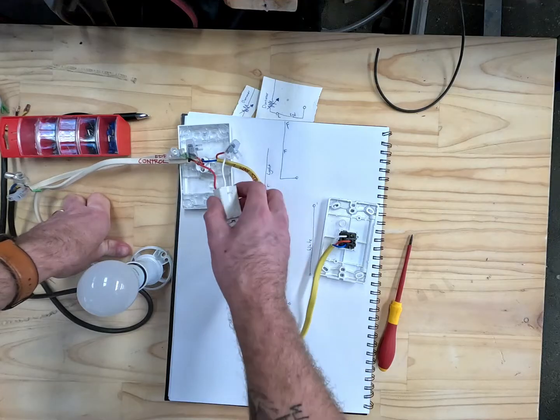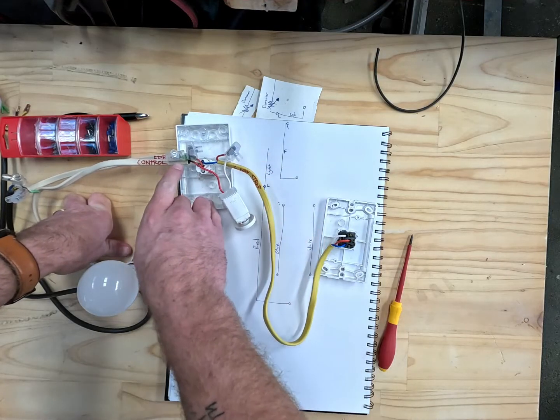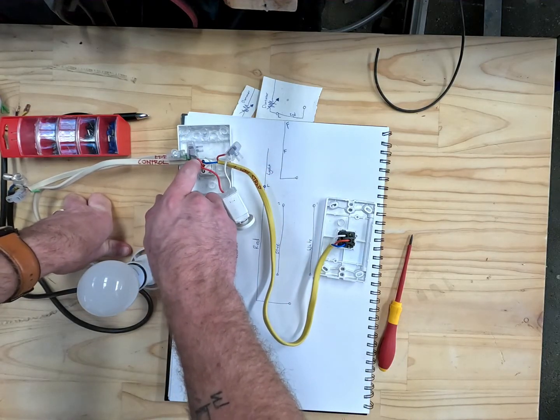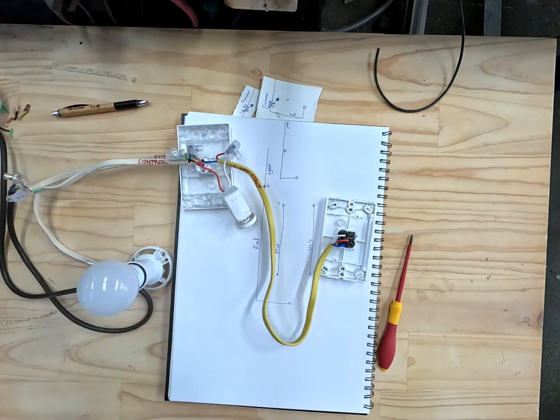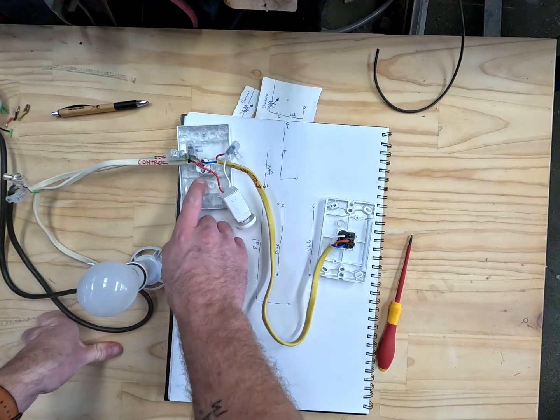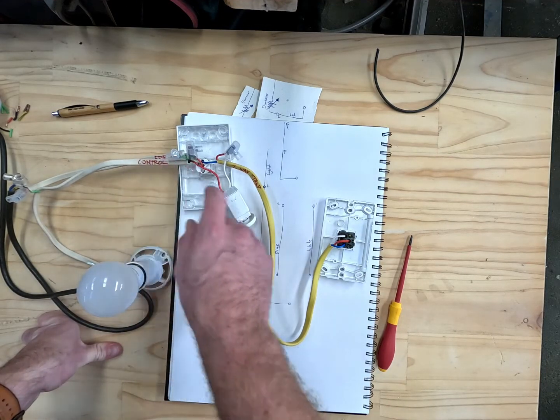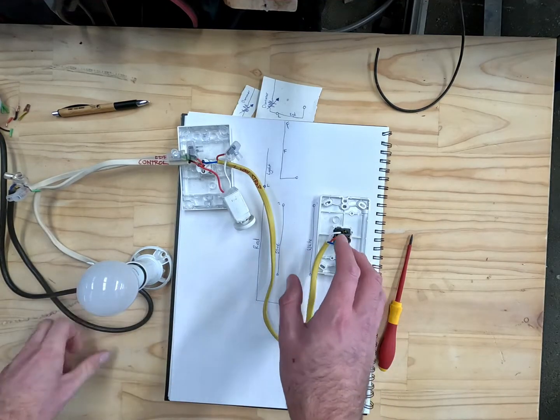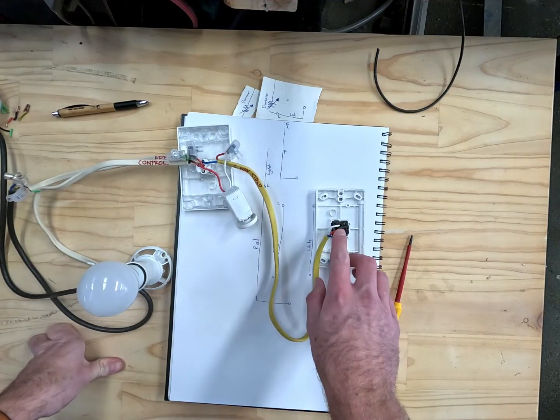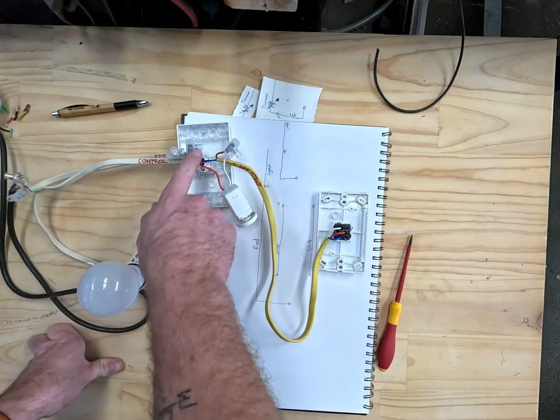So there is one other place you can put this dimmer and that is direct on the feed into the light switch. I wouldn't suggest doing that because then it means that if you turn the light switch off, your dimmer will always be live. So it's far more preferable to have it at the switch here like I showed you or at the switch here.